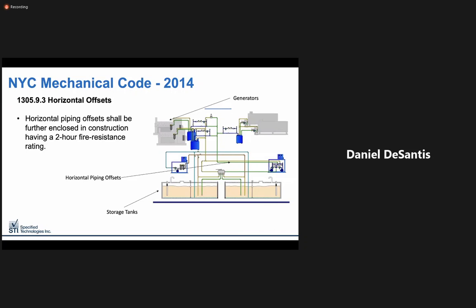Here's the code language for horizontal offsets from the 2014 Mechanical Code of New York City. Horizontal offsets shall be enclosed in construction having a 2-hour fire resistance rating. In certain areas of the city which are prone to flooding, they may require emergency generators to be located on the roof of the building.